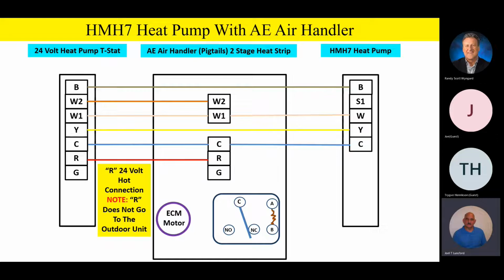Now, please note something. The R terminal connection, or the hot wire connection from the air handler, goes to the heat pump thermostat. It does not go outside. Let me say that one more time. The R terminal does not go outside and hook up to the control board outside. We don't have to have it on the HMH7, so it's a little bit different from our other Champion product. Again, it's different. It's not bad. It's just different. We don't have a 24-volt R terminal going outside. So please remember that 24-volt R terminal goes from the thermostat to the indoor unit only.